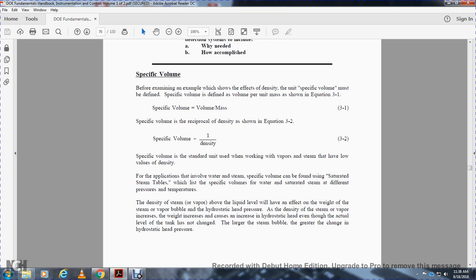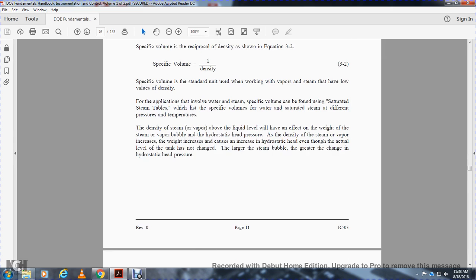The density of the steam above the liquid level will have an effect with the weight of the steam or vapor bubble and the hydrostatic head pressure. As the density of the steam and vapor increases, the weight increases, the hydrostatic head increases, even though the actual level of the tank has not changed. The larger the steam bubble, the greater the change in the hydrostatic head pressure.